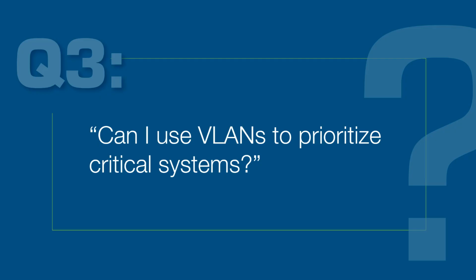QoS is very, very good in the IT world. In the IT setting, it's very, very bursty. There's a lot of unpredictability to the network, to the system. So that's why you want to be able to play around with these quality of service settings. But in an operational technology system, it is highly recommended to not design what we call an oversubscribed network. Therefore, quality of service bits in these cases should not come into play.